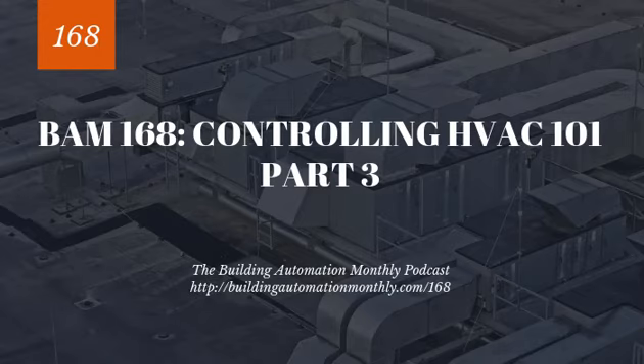Lift is much easier. It's simply the difference between the condenser refrigerant pressure and the evaporator refrigerant pressure. And so this is a measure of efficiency. You want to try to control this so that you are being as efficient as possible with your pressurization of refrigerant as part of the refrigeration cycle. There's a couple different ways you can do this. You can be adjusting temperatures. You can be running different condenser temperatures, but those are some more advanced concepts that are really out of the scope of this podcast. All right.